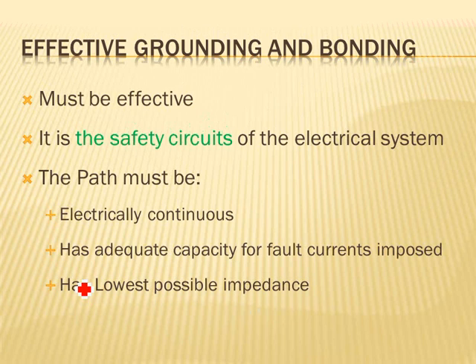What could happen is a bolted three-phase fault. Say you are part of the lockout-tagout procedure that you have to do in a medium voltage system. At the end, the last step in the lockout-tagout procedure is to take phase A, phase B, phase C to the neutral bar and bond them with a bonding cable. That's recommended in NFPA 70E and required on anything higher than 600 volts.